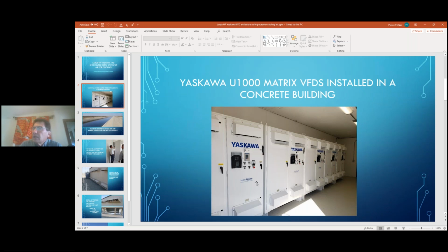At any rate, these are outdoor duty enclosures mounted inside an expensive concrete building. Why did we do that? We did that for thermal reasons. We do not want to exhaust the 80% of the heatsink watts losses, which are connected directly to the diodes and the switching transistors, into the building. Why? We were able to reduce the size of the building, and we reduced the air conditioning load in the building by 60%. Significant cost savings that have nothing to do with the drive, or do they?